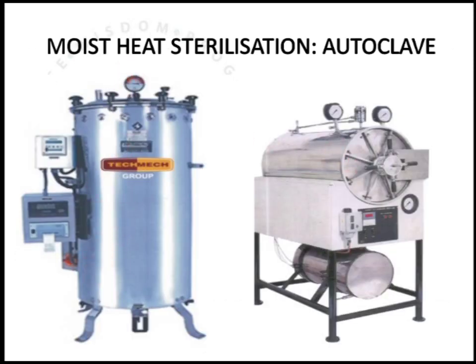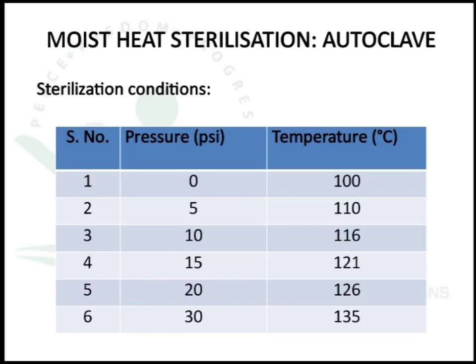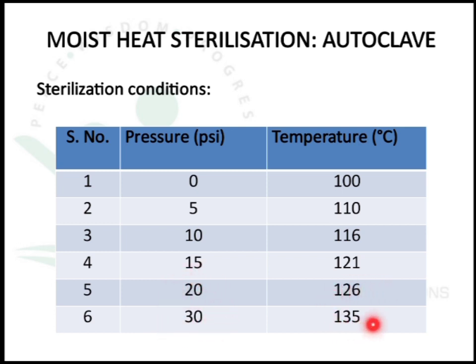By changing pressure inside the autoclave, we can increase the sterilization temperature. At zero or atmospheric pressure, the temperature is 100°C. At 5 psi, it rises to 110°C; at 10 psi, to 116°C; at 15 psi, to 121°C. The usual sterilization condition is 15 psi at 121°C for 15 to 20 minutes. At 20 psi, temperature increases to 126°C, and at 30 psi, to 135°C.